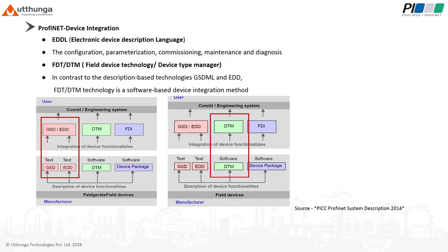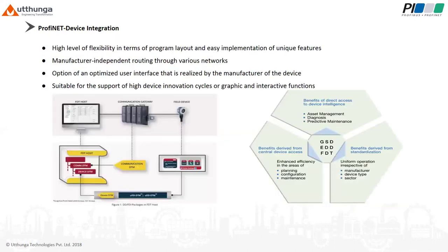And FDT and DTM. FDT is Field Device Tool, while DTM is Device Type Manager. In contrast to the GSD-ML and EDD, FDT and DTM technology is a software-based device integration method. DTM is a software component and communicates with the engineering system via the FDT interface. You can see that in the image. In the image, DTM is used to communicate with the FDT interface and connecting, we are getting the data from the devices.